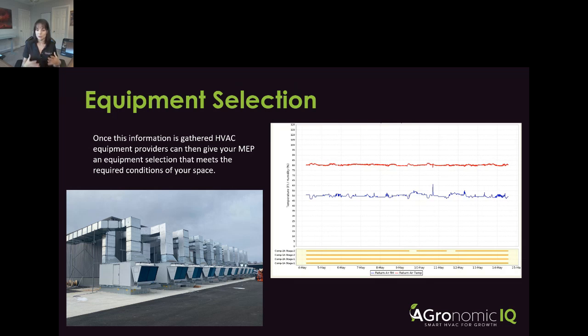These compressors are running comfortably. There's a little bit of intermittent turning off and on. So there's a little bit of extra capacity, but this is perfect for this facility because going into the warmer seasons, this is spot on of what you want your environmental control graph to look like, of how your facility is running.